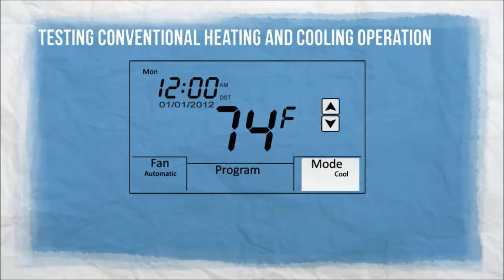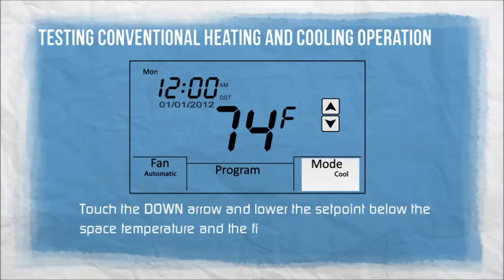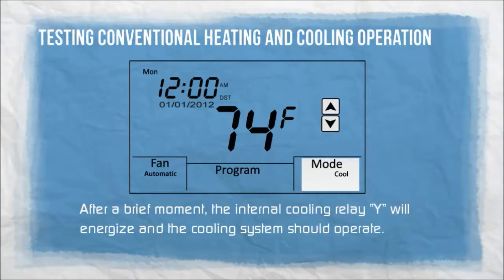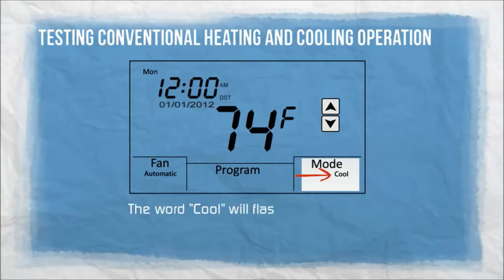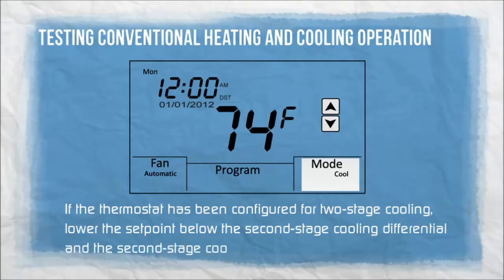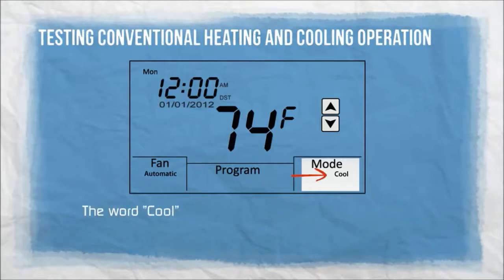Touch the word MODE until the word COOL appears. Touch the down arrow and lower the set point below the space temperature and the first stage cooling differential. After a brief moment, the internal cooling relay Y will energize and the cooling system should operate — the word COOL will flash continuously. If configured for two-stage cooling, lower the set point below the second stage cooling differential and the second stage cooling relay Y2 will energize. The word COOL will flash twice, pause, and repeat to indicate second stage has been energized.